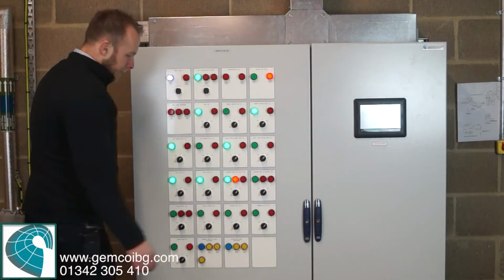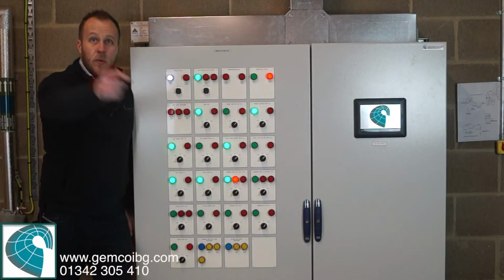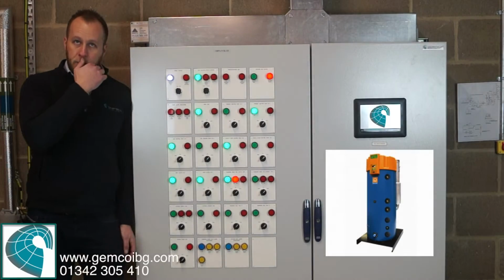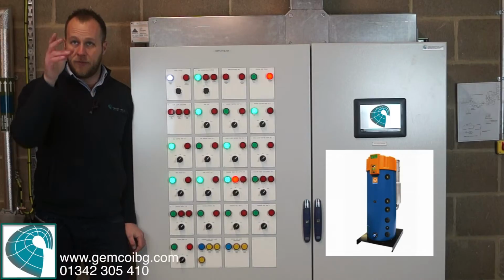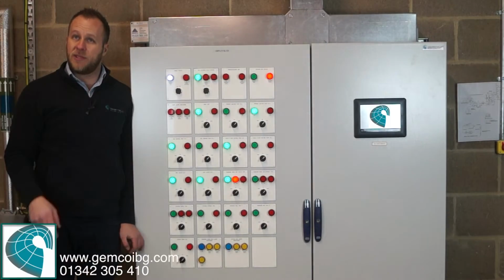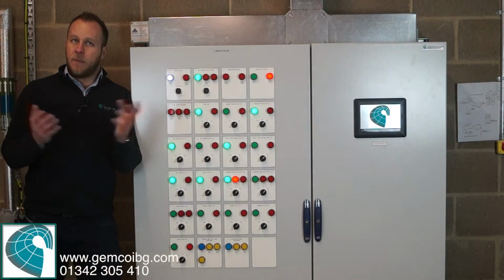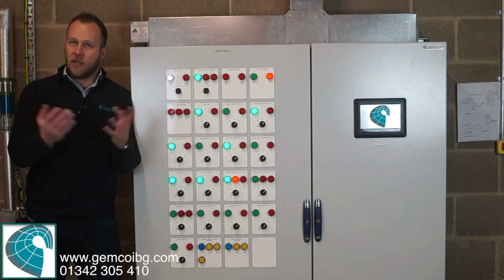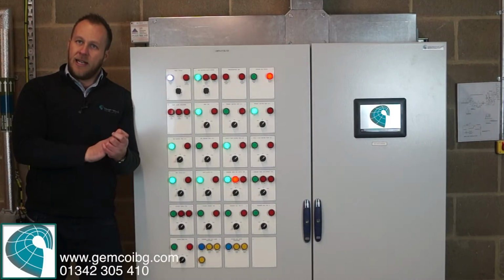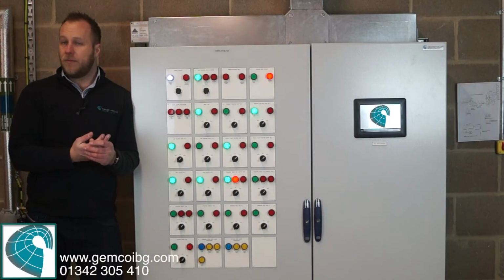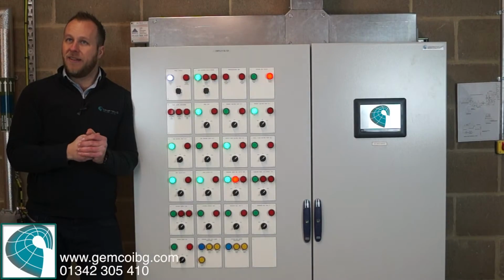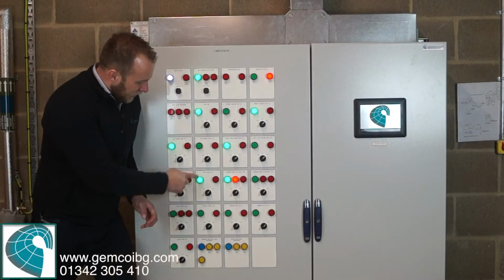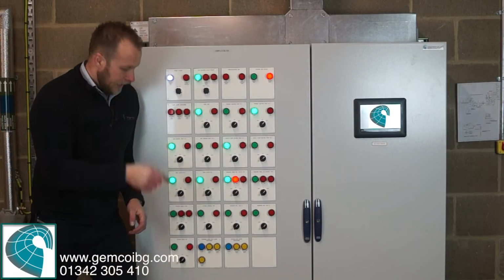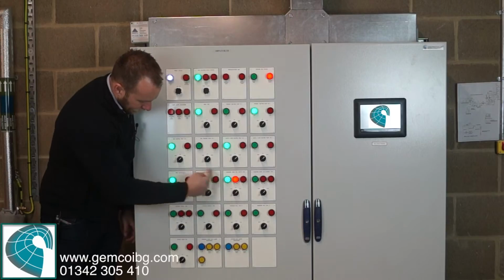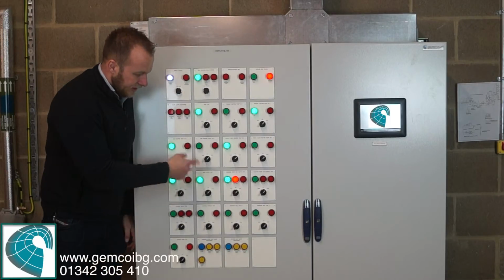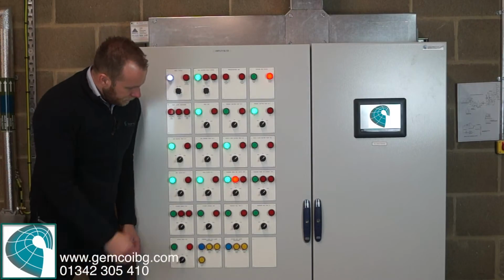Hot water heaters, these are your hot water heaters. They've got a separate time zone, and the times are actually set on the heaters themselves, and they run independently. So they're gas fired. You can run them independently of your heater outside, and they deliver the hot water to your taps. That's about all I can say about that. Again, they've got the thermal links above them, and we monitor them for fault here as well. If there's a fault on one of them, you'll see the red light on the panel.